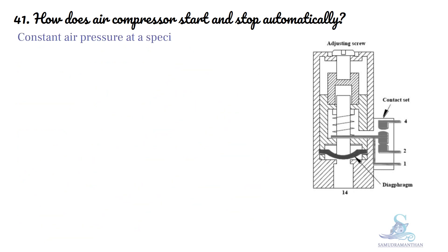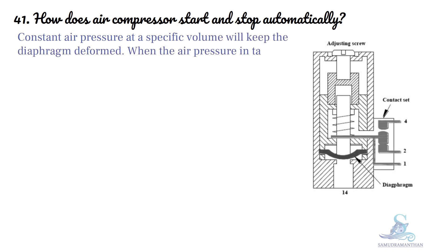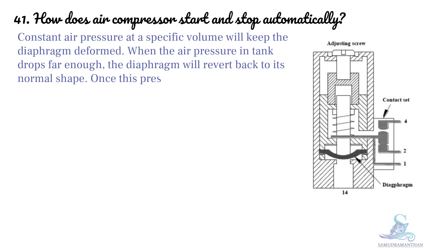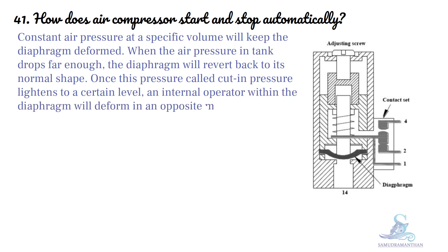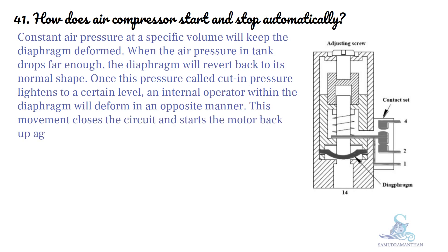Constant air pressure at a specific volume will keep the diaphragm deformed. When the air pressure in the tank drops far enough, the diaphragm will revert back to its normal shape. Once this pressure, called cut-in pressure, lightens to a certain level, an internal operator within the diaphragm will deform in an opposite manner, closing the circuit and starting the motor back up again.